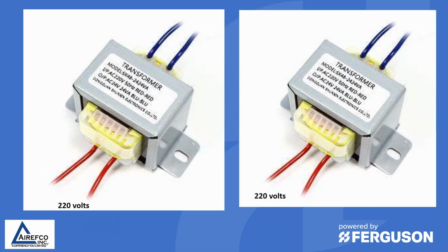So here we have an example of a normal line voltage 220 volt transformer that steps the line voltage down to a 24 volt control. And you'll notice on the data tag on the transformer that the red wires are the 220 volt coming into the transformer, and the blue wires are the 24 volt going out to the control circuit.